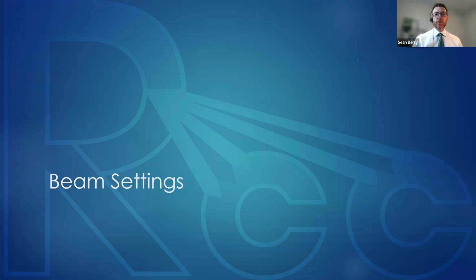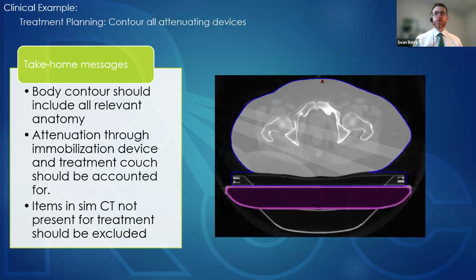Yeah, I agree. This couch here is one that we always add because you can see it throughout the whole treatment. But we've had other machines that have couches with movable bars in the tennis racket, and in those cases we haven't added the couch model, but the therapists have gone carefully to make sure that those bars are moved out of the way of the entrance of the fields. So that's another thing that you could do there if you're concerned about the transmission through the couch.